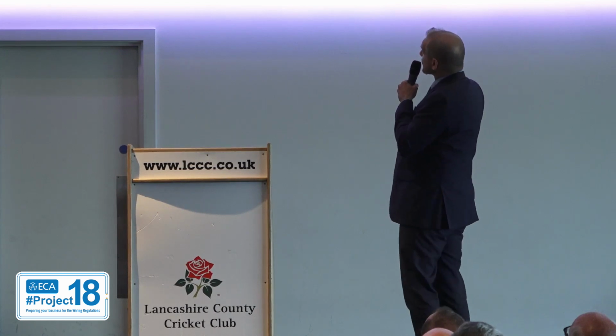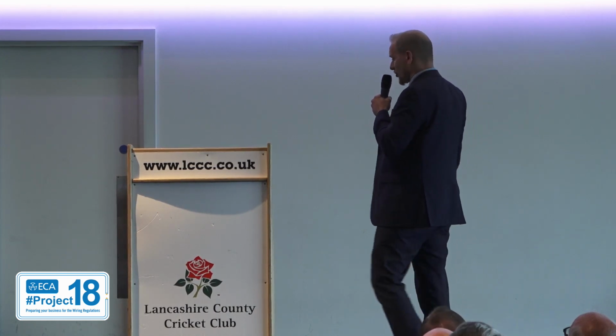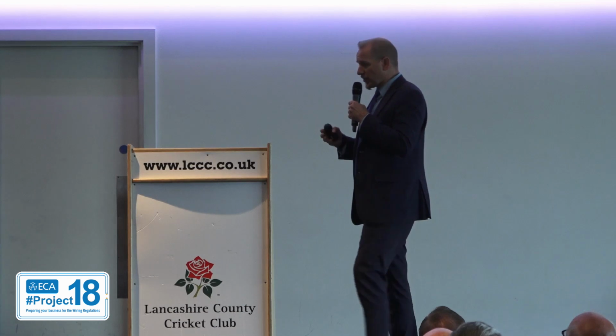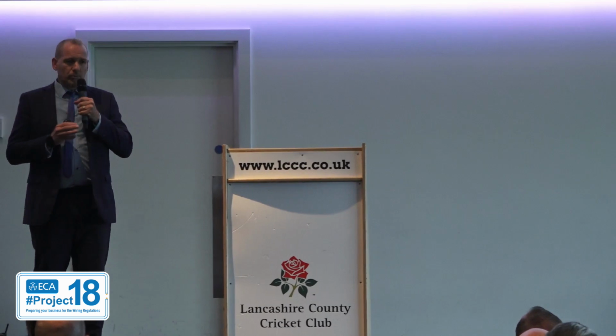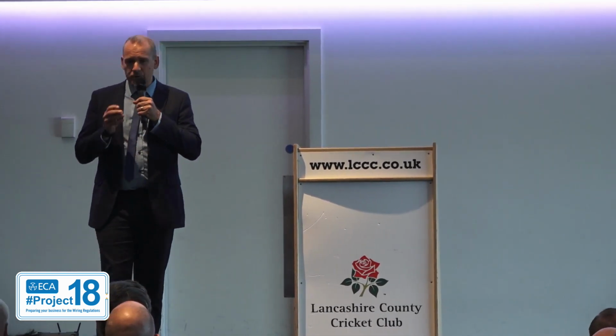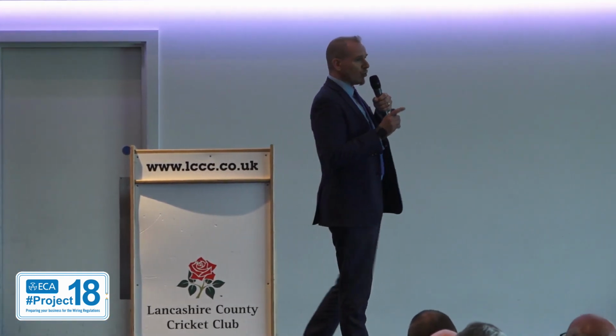So you can see I've put quite a bit of text up here, but I'll try and pick out the highlight points. It talks a little bit about the Construction Products Regulation, and Gary mentioned those earlier in terms of cables. Just to give you a pointer on that, because we don't manufacture and supply cables, but this is quite important. Cables that you buy now under the Construction Products Regulation have to be accompanied by a document called a DOP, which is a Declaration of Performance. A DOP document covers all the technical characteristics of that cable.